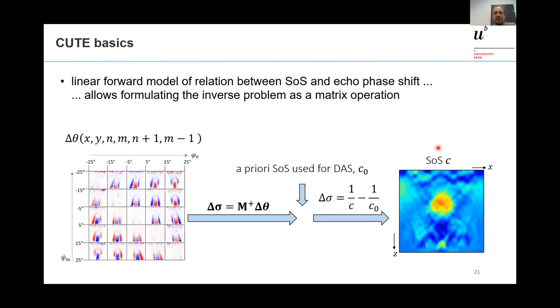Departing from the echo phase shift data, we use this formula to calculate delta-sigma. Then, combining this with our initial assumed speed of sound C0 used for delay-and-sum, we recalculate the actual speed of sound. You can see nicely that an area with higher speed of sound in the background produces this echo phase shift data, and the reconstruction correctly recovers it.